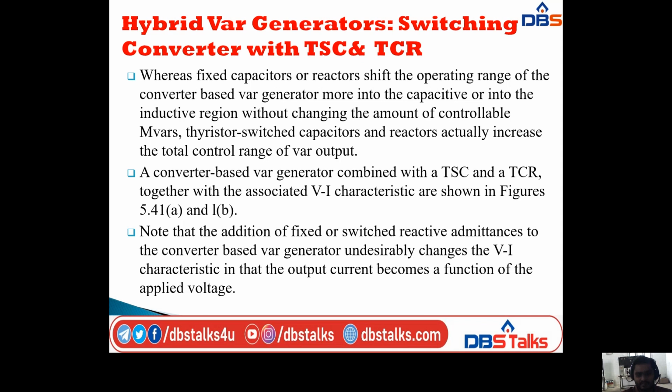Compared to those two, fixed capacitors or reactors shift the operating range of the converter based VAR generator more into the capacitive or the inductive region, without changing the amount of controllable MVAR. Thyristor-switched capacitors and reactors actually increase the total control range of VAR output.